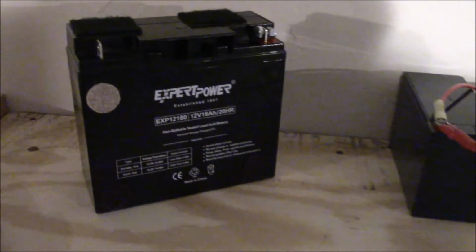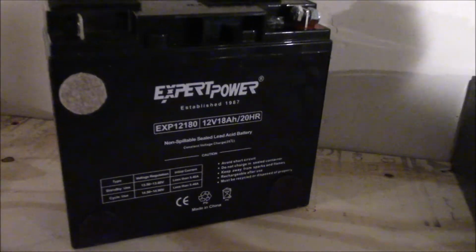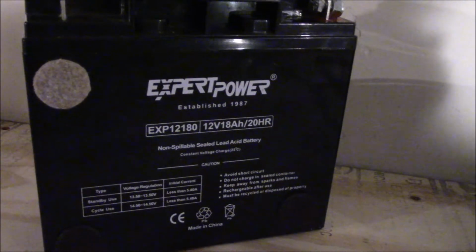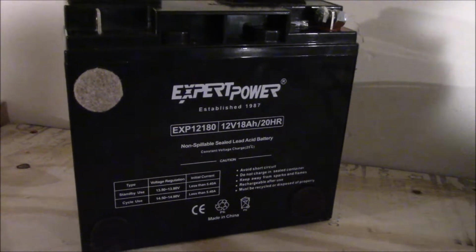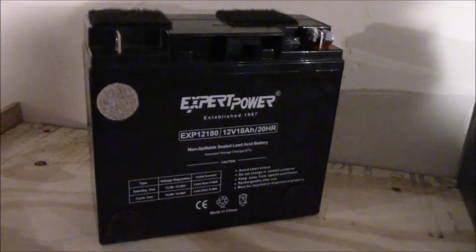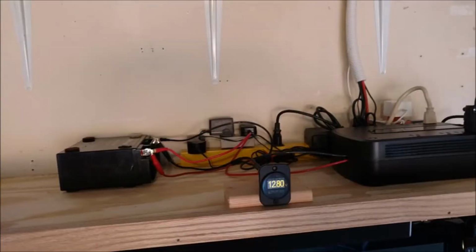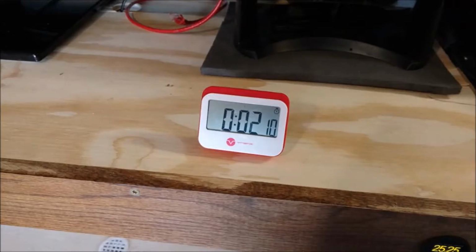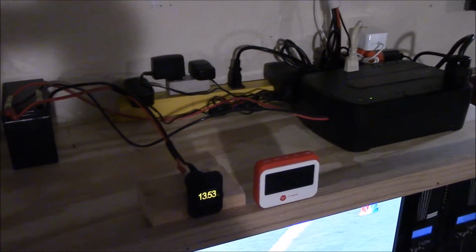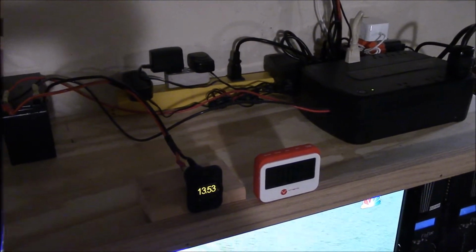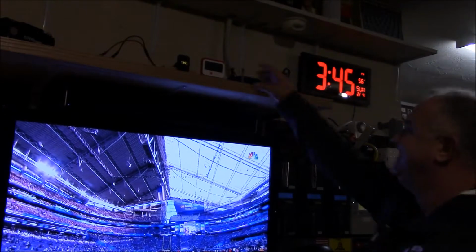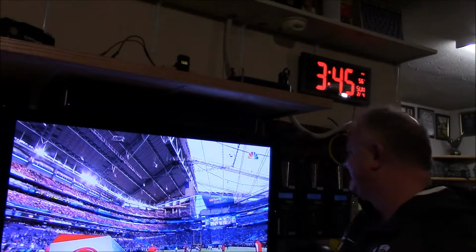And this is the battery that absolutely failed. I didn't do a video on this, but I can tell you, this thing is just a big hunk of junk. So here I am testing it. I had high hopes, you know, try to get at least 14 minutes, but it only ended up being 2 minutes before the thing kicked off. So I rewired the original battery back into the APC UPS and redid the test, just wanted to make sure that I wasn't dreaming.